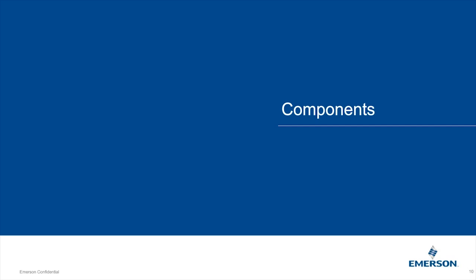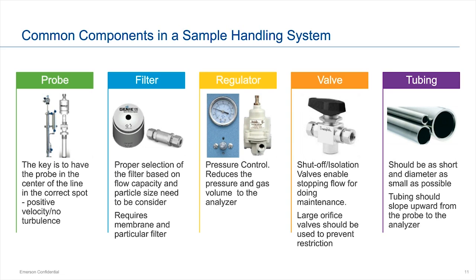Moving on to components. There's a wide variety used in a sample handling system. The first is the probe — it extracts what's flowing in your stream or pipe. There are many types: standard probes, direct drive probes, probes with heated regulators, probes with membranes. The right choice depends on your source conditions, temperature, pressure, and contamination in your system. We don't manufacture probes but work with several probe manufacturers and offer them through resale.